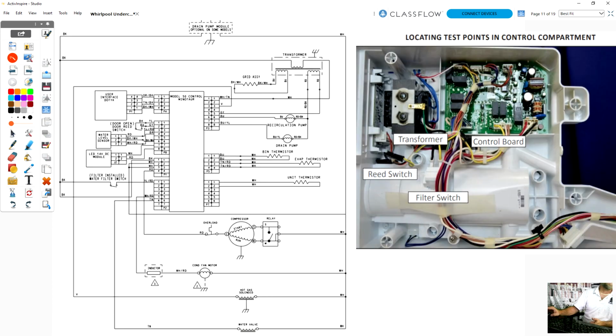So here is the schematic and a breakdown of the parts. The unit has an external transformer. This is called a step-down transformer, and that is located right here. Let me get my marker. That's located right here. It's got line 1, which is black, coming in, and this is neutral, which runs into the board here. And this should have 120 volts all of the time. Okay? We have 2 outputs, the blue wires and the red wires.